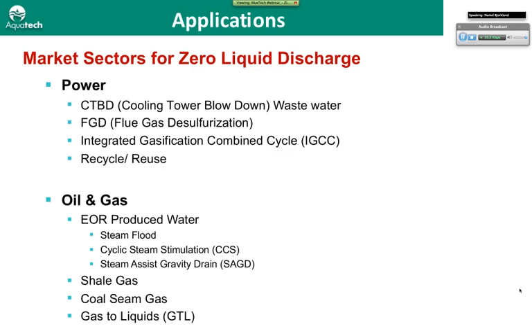Some of the market sectors we see: ZLD pretty much grew out of the power market and was developed around treatment originally of cooling tower blowdown wastewater. Power plants use large amounts of water, and the cooling towers cycle up in concentration, and that blowdown, if they do not have a discharge permit, then a ZLD plant is in some cases installed to recycle water, and what leaves the plant is a solid stream.